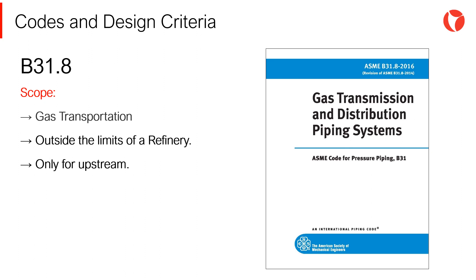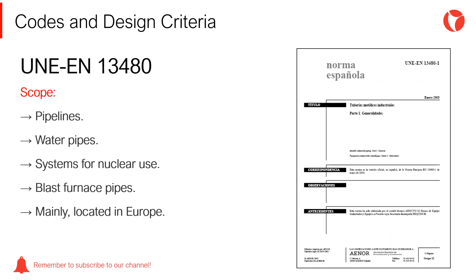The piping design code ASME B31-8 is applicable to gas transportation pipelines outside the limits of a refinery and only for upstream. The European equivalent to ASME B31-1 is the EN 13480 standard. It is a very broad code, covering different types of industrial plants and piping systems.